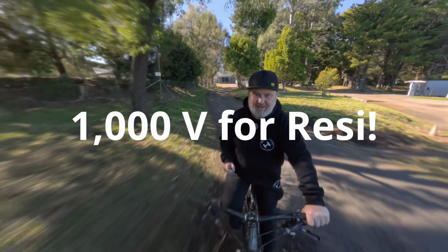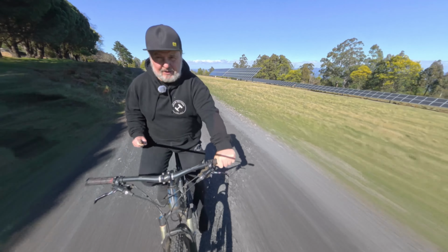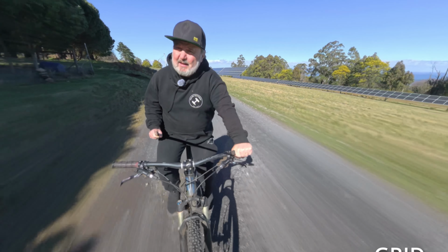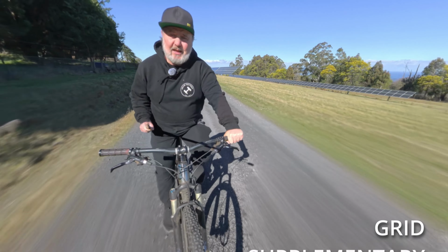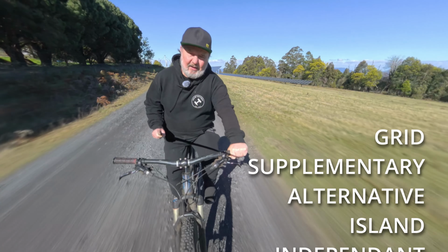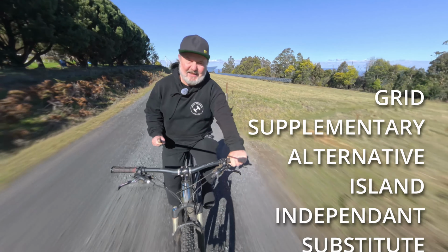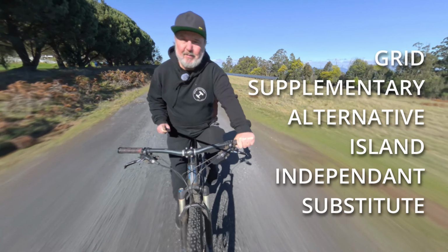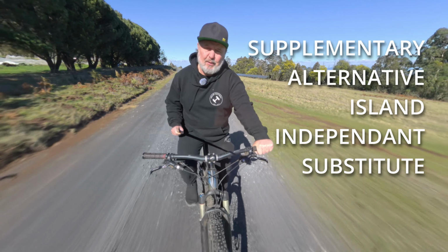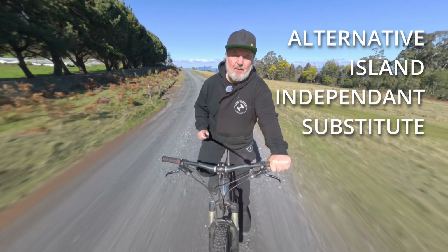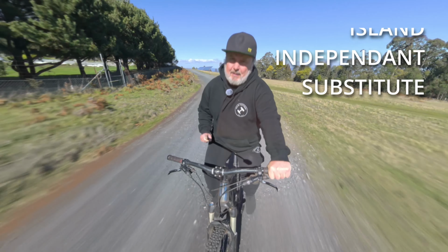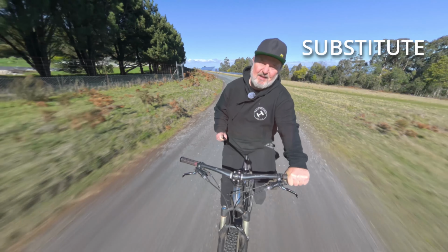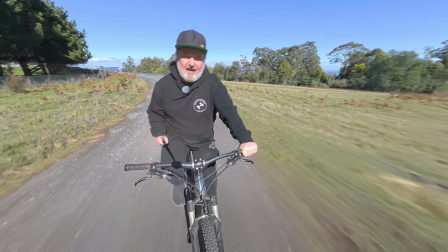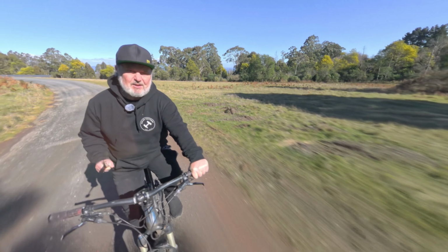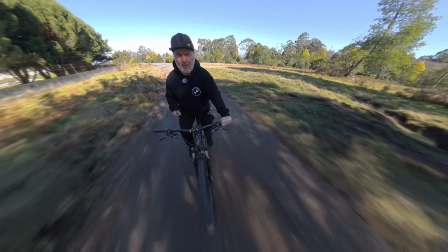The third point is we're changing a lot of the names for supply. Part of that is to line up with the terms used in AS/NZS 3000, things like alternative supply. But we've now got, I think, five or six - there's a lot of them. We've got supplementary supply, which is replacing the old solar inverter supply name. We've still got grid supply. We've got independent supply, island supply, and alternative supply. So there you go, there's a whole bunch of them. I'll put them on the screen. I still have trouble remembering them all.